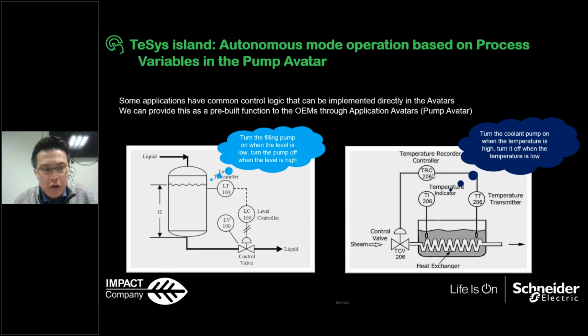Okay, for these process variables, when the fluid level is too high, you can actually input different ultrasonic sensors. And if it's too high, then you can stop the pump. If it's too low, then you can kick off the pump, and it can be achieved automatically inside the digital island without the PLC. So this is what we call the autonomous control, and it may benefit customers, especially the OEMs or the small and medium-sized pump panel builders, because you no need to have a PLC to control the system.